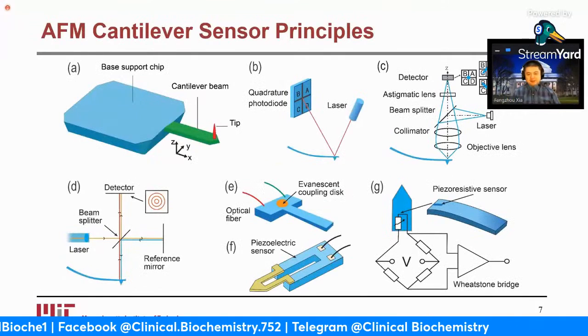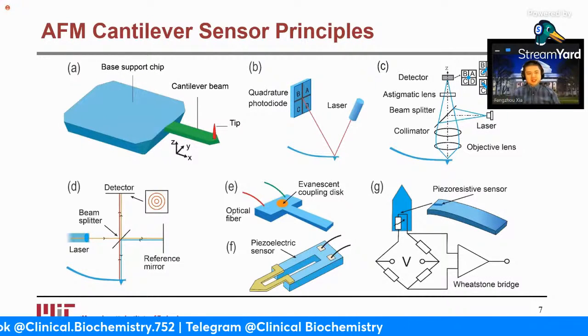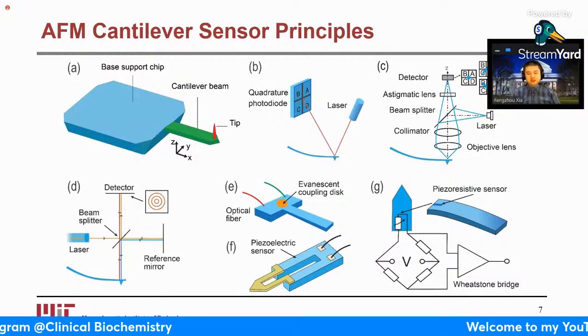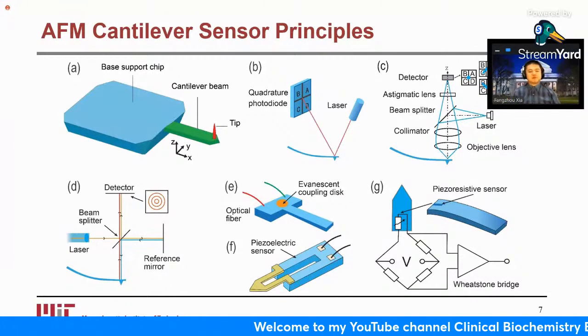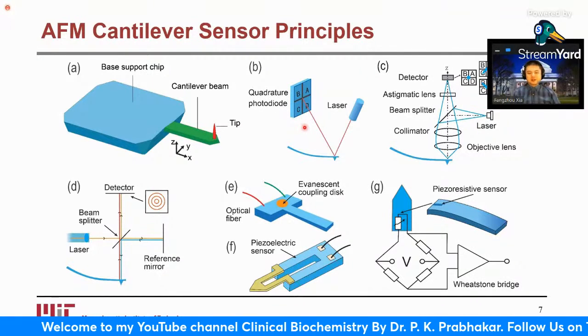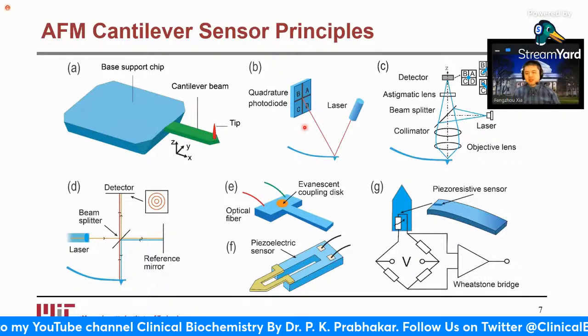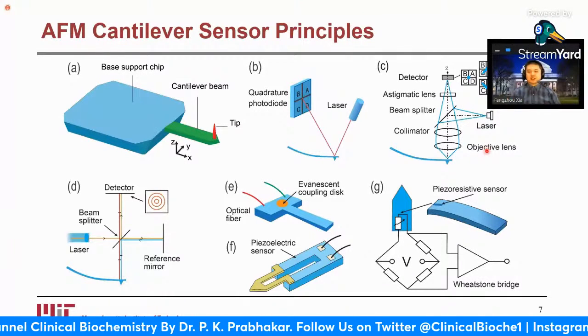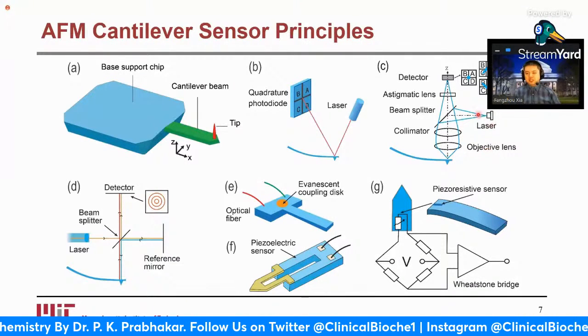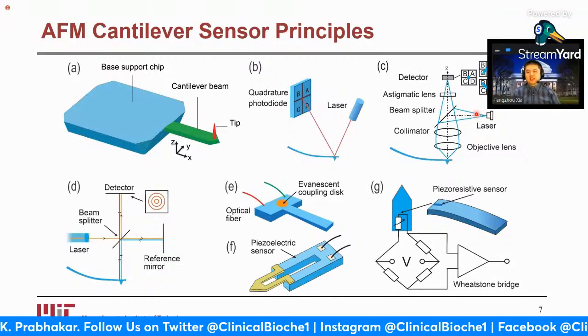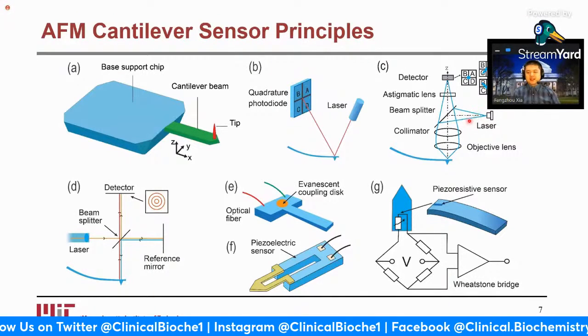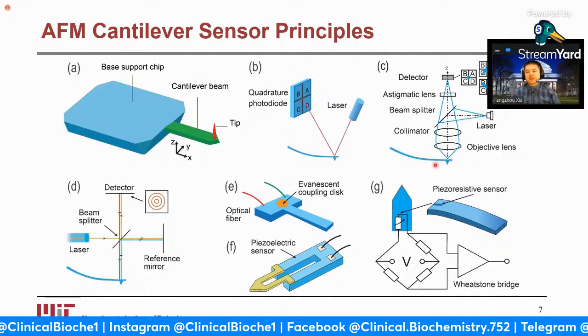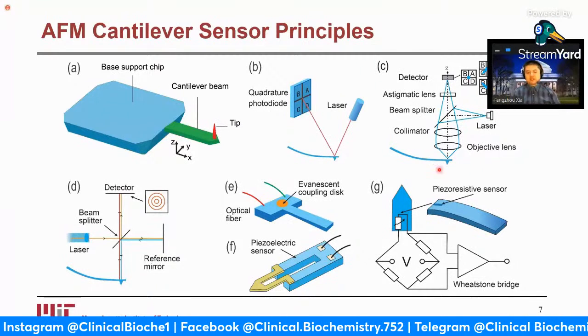So I actually have a paper published summarizing the different sensing and actuation principles. The dominant ones, not only in the commercial systems but also in research, are the 6 different sensing principles, starting from this basic quadrant photodiode-based optical beam deflection system. People have been using this so-called astigmatic detection system, which is a typical principle used in getting DVD or CD drive signals. And then it can be similarly applied to the AFM cantilever to measure its deflection.